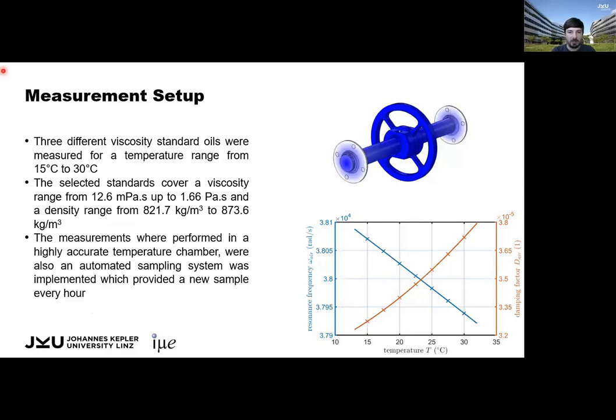For the measurement setup, we placed the whole sensor and an automated sampling system into a highly accurate temperature chamber and measured different viscosity standards at different temperatures.